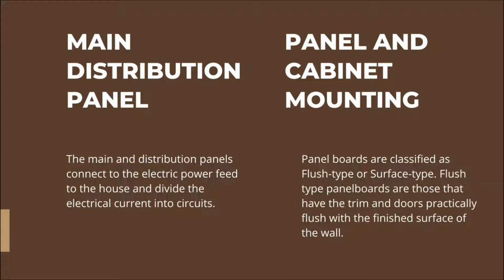Panel and cabinet mounting. Panel boards are classified as flush type or surface type. Flush-type panel boards are those that have the trim and doors practically flush with the finished surface of the wall. So, the difference between surface and flush-mounted panel: a flush-mounted panel goes in the wall. A surface-mounted panel goes on the wall. The difference is in the cover. Usually, surface covers are the same size as the outside dimension of the panel itself. A flush cover is larger to cover up the edge of both the panel and the wall material.